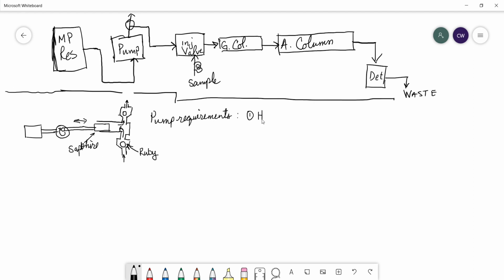The first is they must be able to handle pressures up to 6,000 psi. Typically, if you manage to get a pump up to 6,000 psi, the pump will be fine. Your lines will explode first, because your fittings or your actual physical line material will not be able to handle that pressure, and so it will fail mechanically well before you reach 6,000 psi.